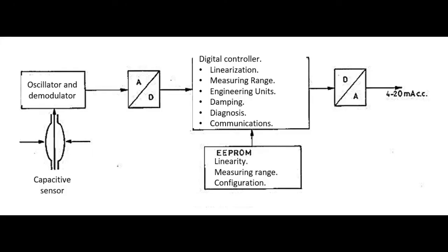A circuit with an oscillator and a demodulator transforms this variation of capacitance into an analog signal, which in turn is converted into digital and goes through an intelligent microcontroller that converts it into an analog output signal of 4 to 20 mA direct current.